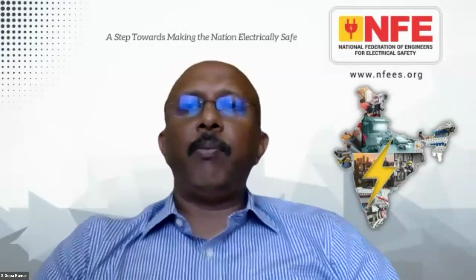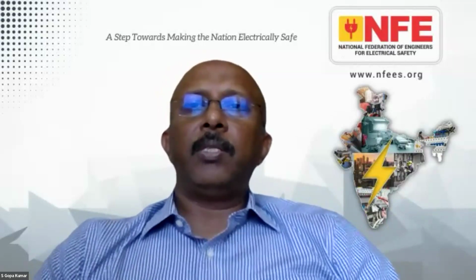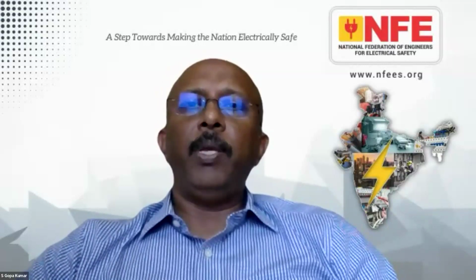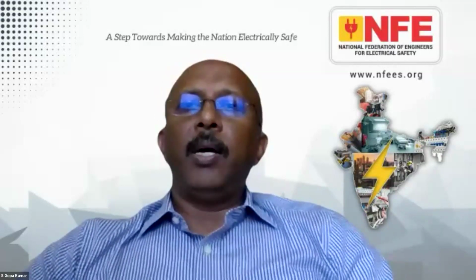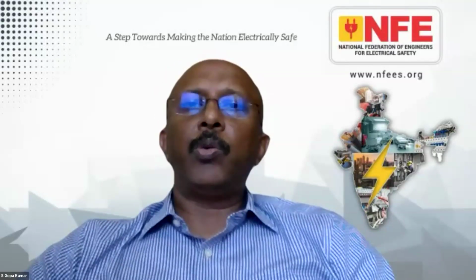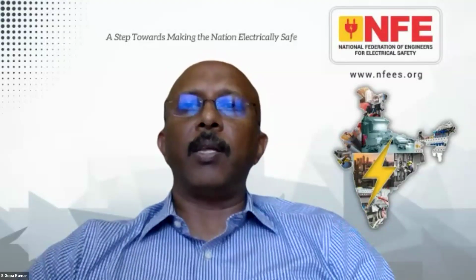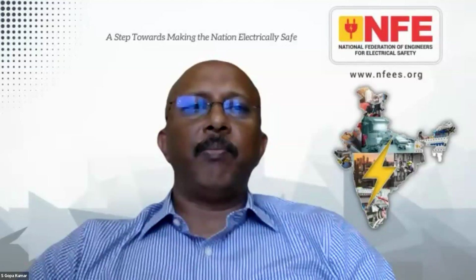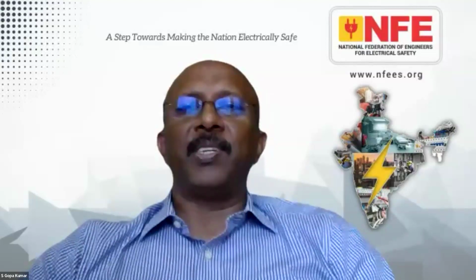So we have the next question from Mr. Kamlesh Kumar. Three-phase system loops are made of RY, YB, BR, RE, RN. In this, which measured value should be considered to verify the result? Probably all of them, depending upon the situation. Correct. So first, if the resistance is low for that particular electrical installation, then I think you have to consider all three. If any one of the phases has high resistance, then that is the place where correction needs to be taken care of.